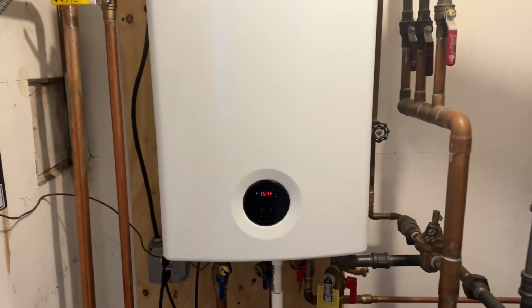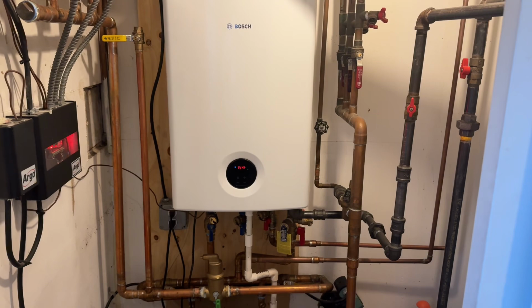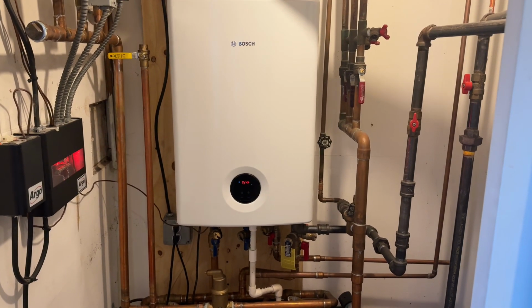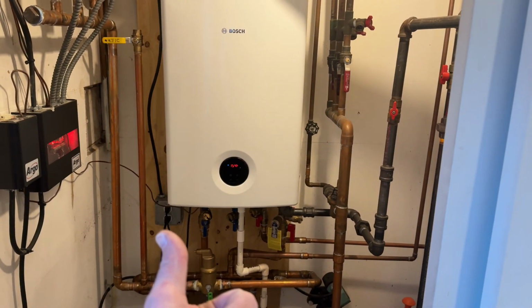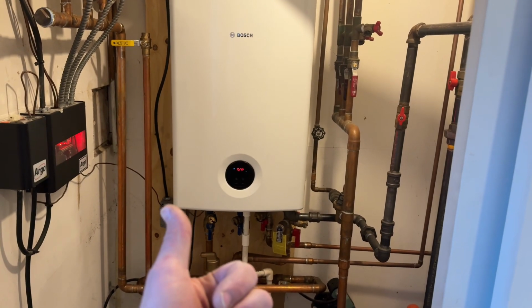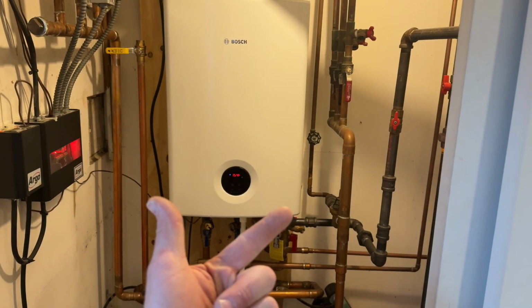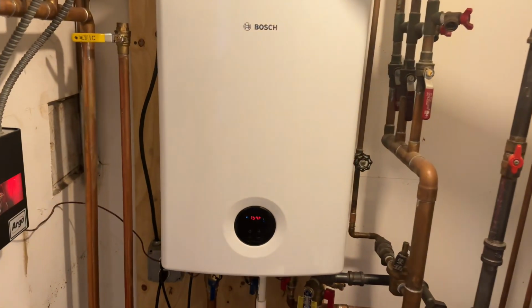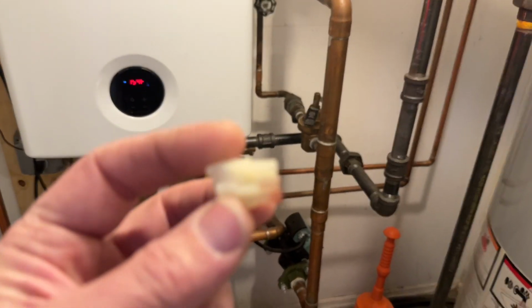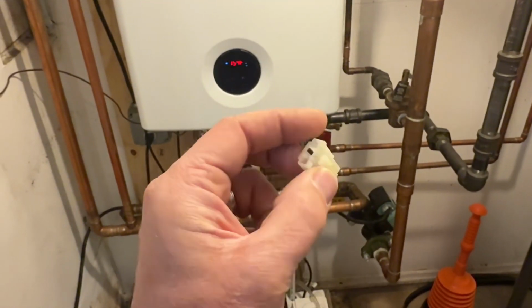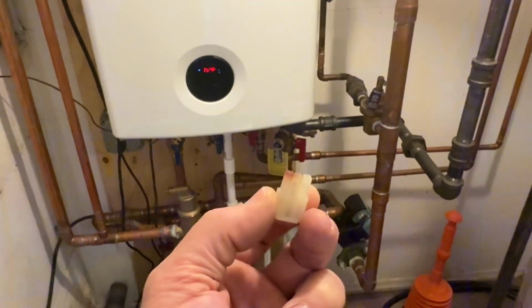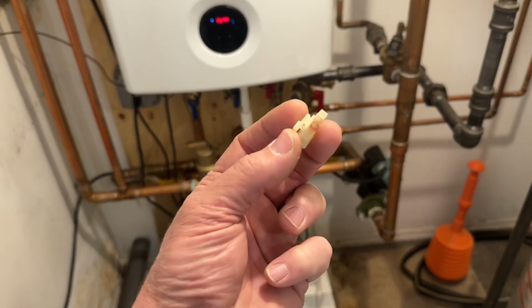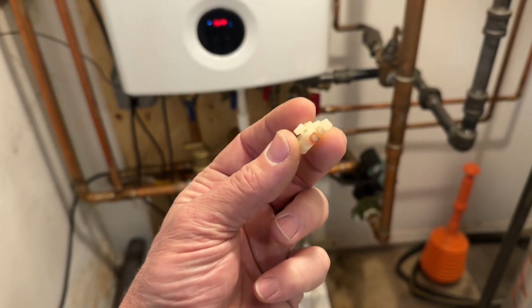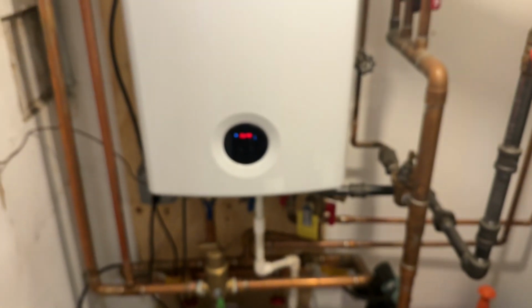If it is, replace the temperature sensor. But also, you could have a need to clean and descale the heat exchanger, or you could have bad circulation or something restricting flow. So, several weeks ago on this particular model, a leak developed on the inside of this unit, and another contractor found this Molex connector that connects to the internal circulator. Got some water on it, got wet. So let's take a peek under this hood and see what's going on.